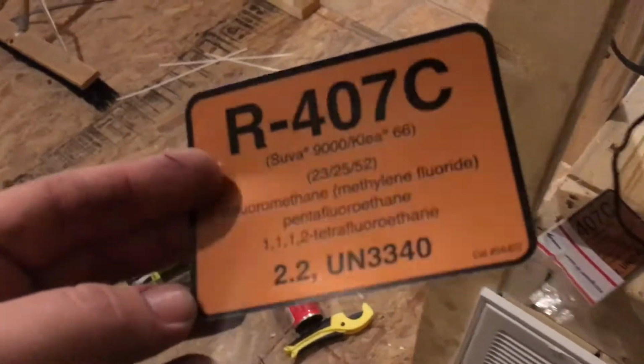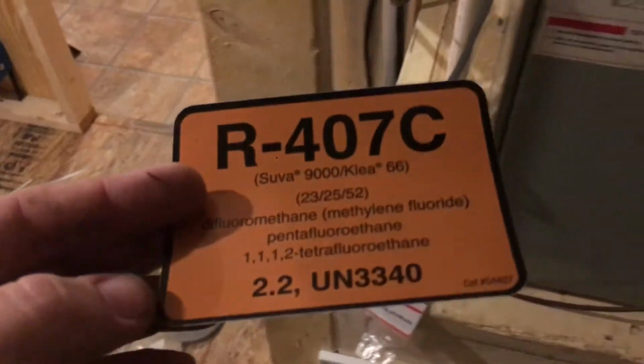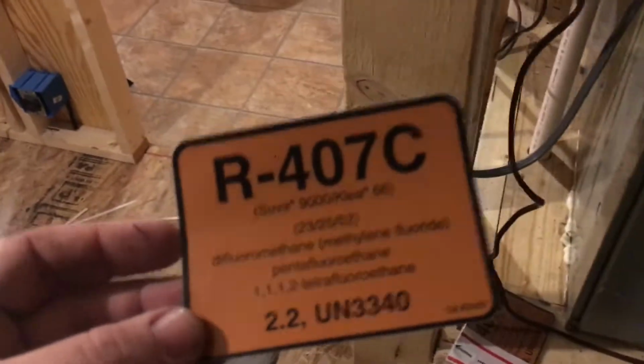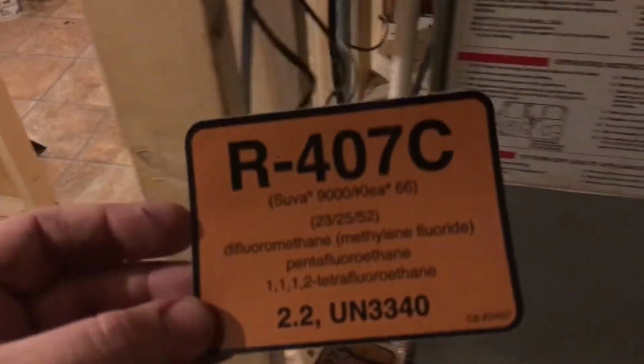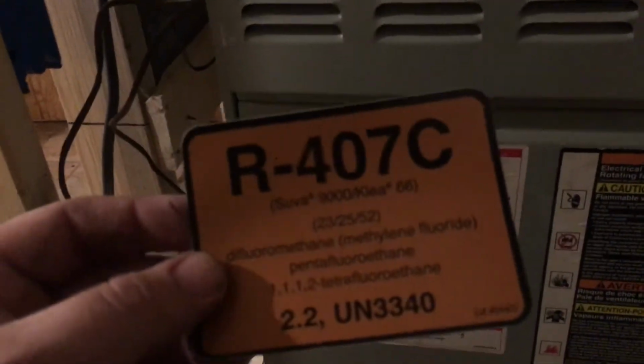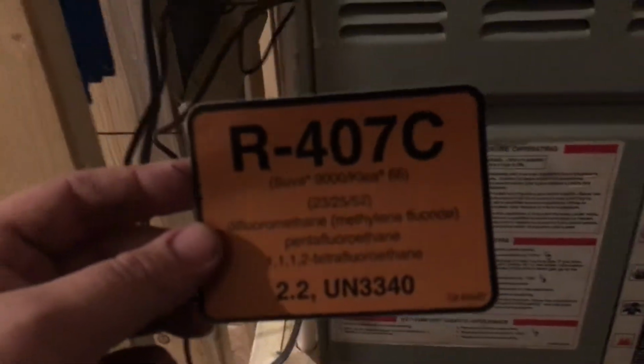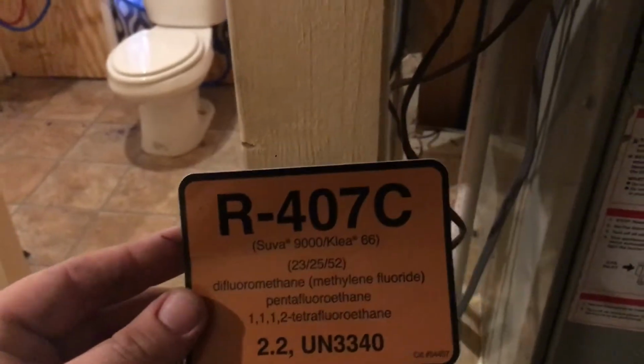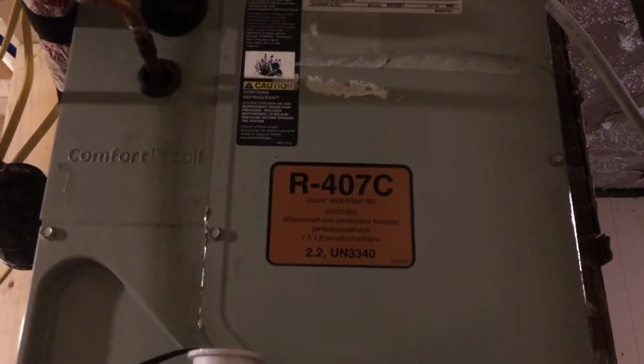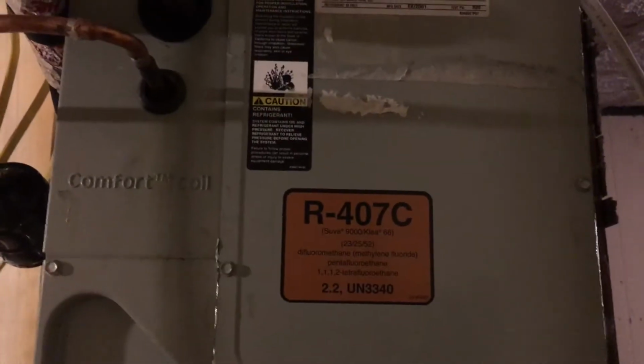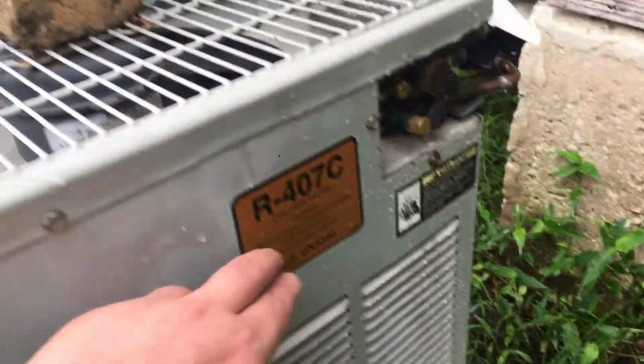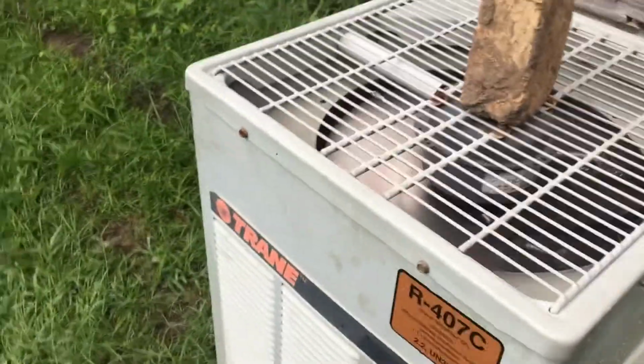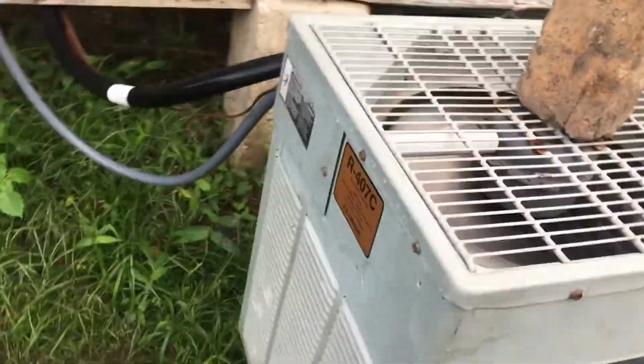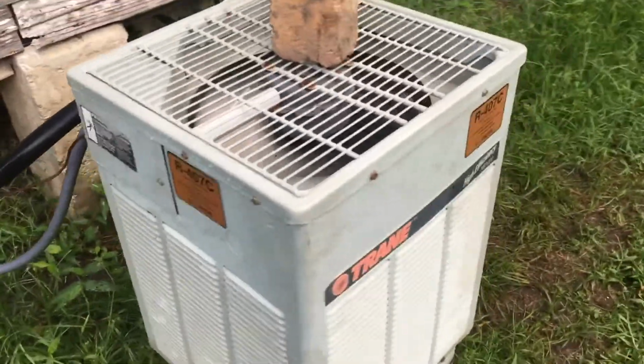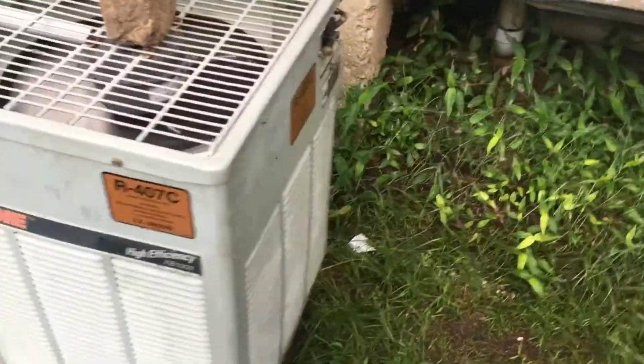Now there's one last very important detail. Anytime you change over the refrigerant, you need to label the system to the new refrigerant so that the next guy who works on it will know what you did, will know what's in it. As you can see, I labeled the condenser unit in 3 places. That way you can't possibly miss it.